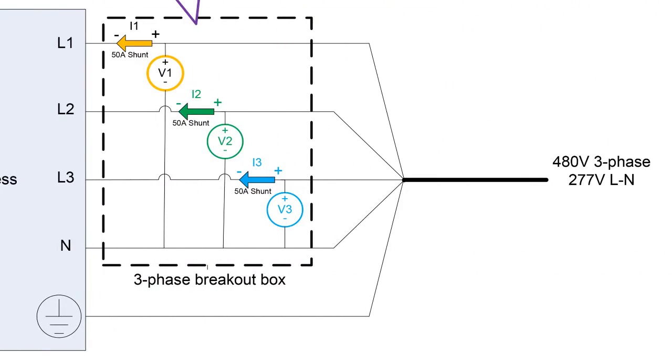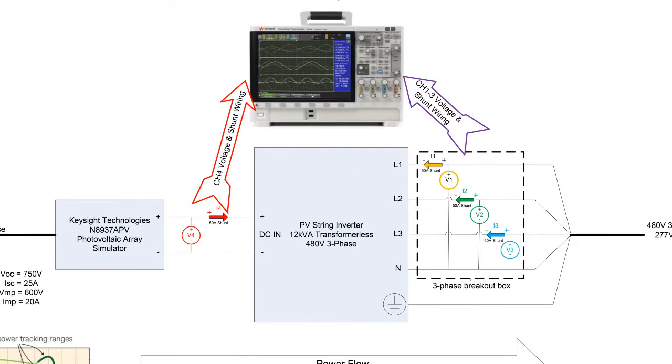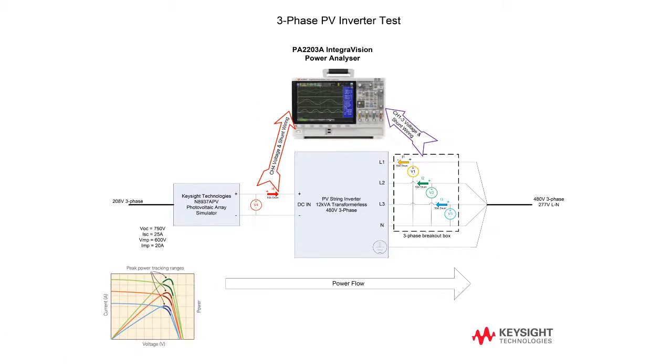The output is connected to 480 volt three-phase and I'll be measuring the output of the inverter using channels one, two, and three on the three phases connected to neutral. On the input I'll be using channel 4 to measure the voltage and current of the DC input to the inverter, and these are wired into the power analyzer. So that's our configuration.